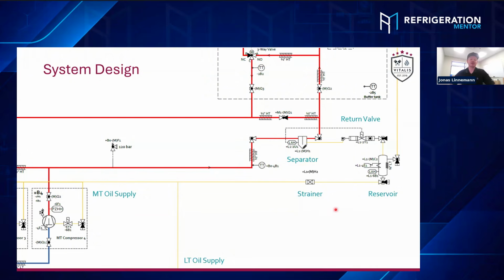I mean, you just need to isolate the valve around the strainers, especially this one. This is the most important strainer here because it's the first in the oil line. And it's basically the same thing. You isolate, you try to drain as much pressure as possible out of that little section into the reservoir, isolate downstream, and then make sure to depressurize the section. And then it's basically just opening a strainer body and cleaning the mesh and changing it if necessary, right? So that's pretty normal mechanical work.